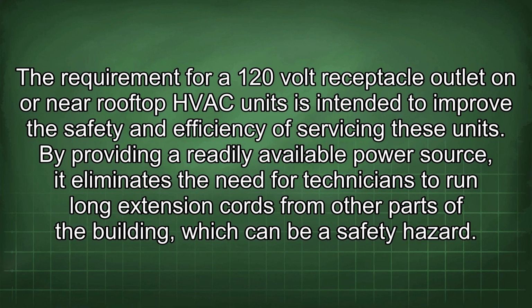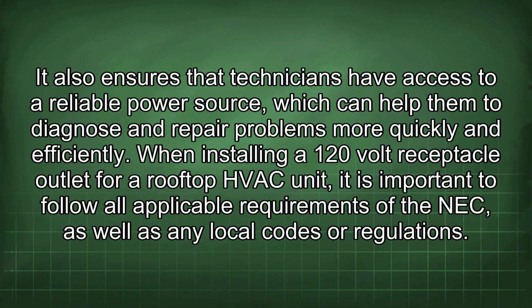The requirement for a 120-volt receptacle outlet on or near rooftop HVAC units is intended to improve the safety and efficiency of servicing these units. By providing a readily available power source, it eliminates the need for technicians to run long extension cords from other parts of the building, which can be a safety hazard. It also ensures that technicians have access to a reliable power source, which can help them to diagnose and repair problems more quickly and efficiently.